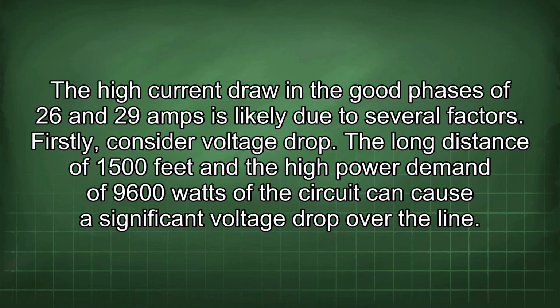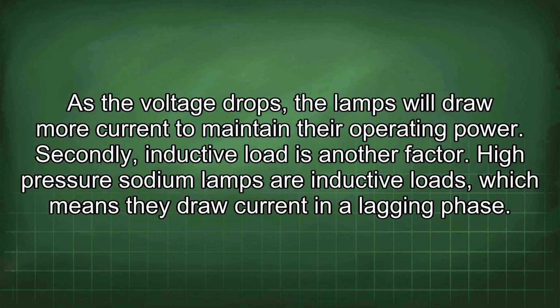The high current draw in the good phases of 26 and 29 amps is likely due to several factors. Firstly, consider voltage drop. The long distance of 1500 feet and the high power demand of 9600 watts of the circuit can cause a significant voltage drop over the line. As the voltage drops, the lamps will draw more current to maintain their operating power.